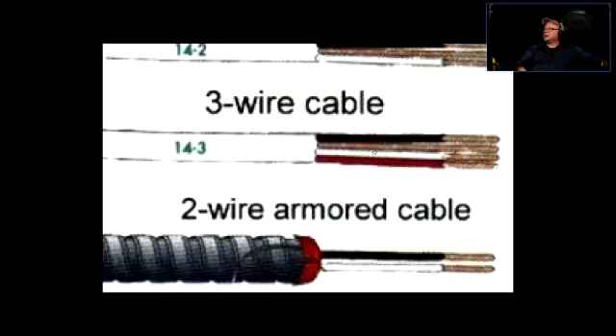What makes it a neutral wire? The neutral wire is at the same potential as ground or bond. So if you put a voltmeter between this white wire here and this bonding wire, you should get no voltage reading at all. It has the same potential as the grounding wire.